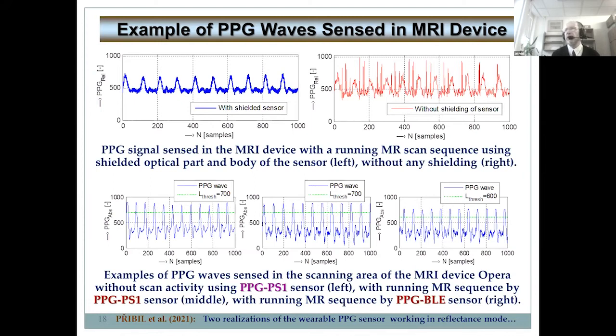The influence of radio frequency disturbance on PPG signal sensing is demonstrated by the 2 upper graphs. They practically confirm the necessity of shielding all parts of the PPG sensor. Below are shown examples of PPG waves sensed in the scanning area of the MRI device without scanning activity. This is the graph on the left. With a running scanning sequence using the first realization of the PPG sensor, this is the middle graph, and with a running MR sequence using the PPG sensor realization with the low energy Bluetooth connection.